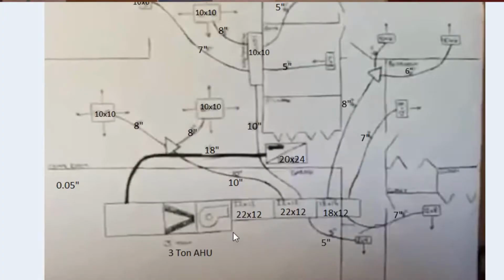So, moving forward, we've got a 3-ton unit. It's pushing air into what looks like about 12 feet of duct trunk. I'm assuming this is duct board just by looking at the system. I like to call these rat's nests, but there is actually a name for this type of duct system, and I have yet to find one here in Pennsylvania, and it's probably for good. We don't see them a lot around here. I've run into a few of these in my entire life, and they give you problems.